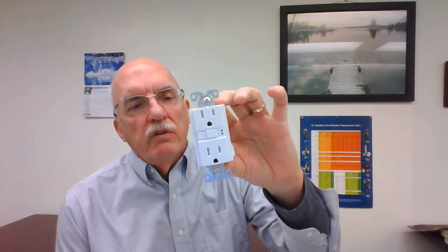So, like I said, the two-prong receptacles, if you're at least on the 2014, you can no longer replace that two-prong with a two-prong. Not allowed. In the past, it's been acceptable to the code to replace the two-prong with a three-prong, as long as you put in this GFCI type receptacle outlet. The code said you could use one of these, wire it line and load on this GFCI type and protect the downstream, as long as you put those little stickers on it, they come in the box. Please stop throwing away the instructions that come with these receptacles and switches and lights and all that. Read them, please.